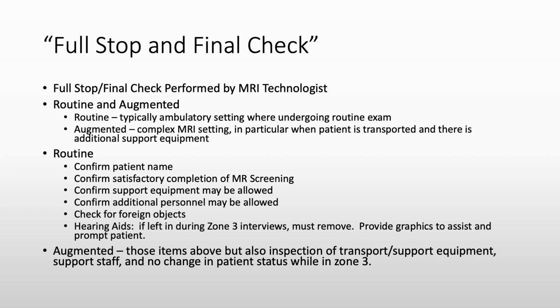At this time, the MRI technologist also checks for any hidden foreign objects. This final check is completed before allowing the patient to enter the room. In particular, if hearing aids were left in during the Zone 3 interviews, make sure that those are removed. Now, if you are in an augmented setting, which is one where a more complex exam will be completed, you will need to complete a more thorough evaluation. The augmented portion will include the routine checks, but also inspection of the transport and support equipment, screening of support staff, and verification that there is no change in patient status while waiting in Zone 3. See the ACR Safety Manual for further guidance on augmented procedures.